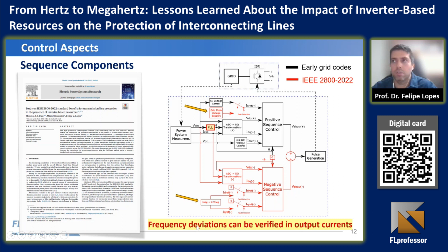This is the problem of frequency deviations on distance protection elements. The first time that I read about such a problem was in this paper, which was written by Bogdan. It is a very nice paper, in my opinion. I had good times reading it. He was very clear in his explanations when he said that there is a rotating trajectory that can take place depending on the fault resistance and the frequency deviation between the contributions that come from the IBR and from the grid. In this paper, he also proposed some new operating characteristics, including what he called a weak infeed distance element.